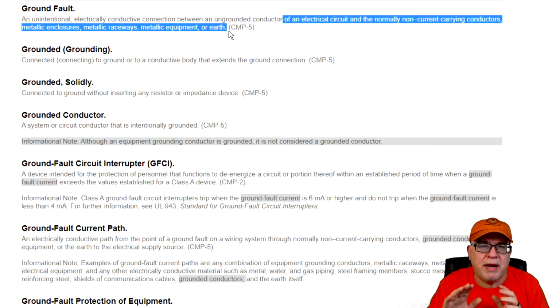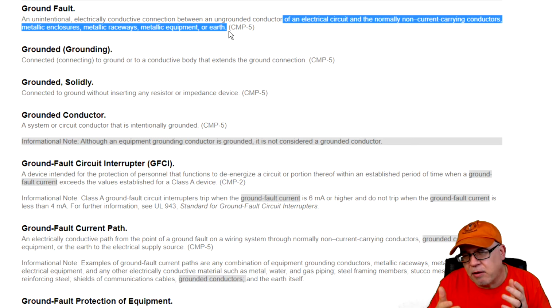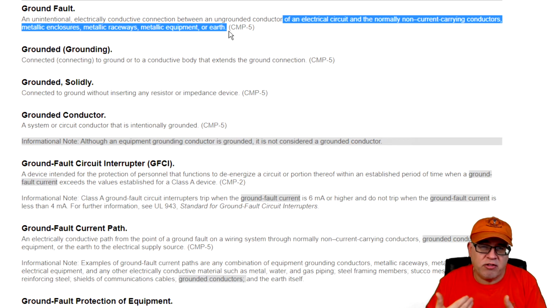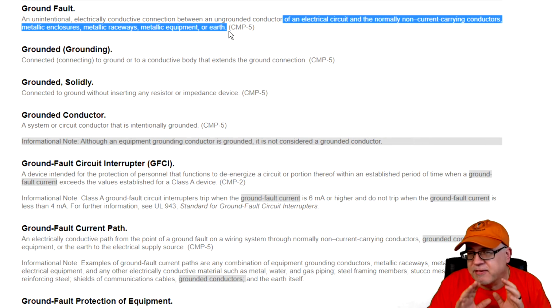There's an important reason why we have to have a low impedance ground fault current path. I guess now we don't say effective, we just say a low impedance ground fault current path. And when we do that, we allow that current to get back to the source, skyrocket at the point of the ground fault, and that's how we have overcurrent devices trip. That's how we have GFCIs operate and function, because they can detect leakage on an unintended path. All those things create a safe system.